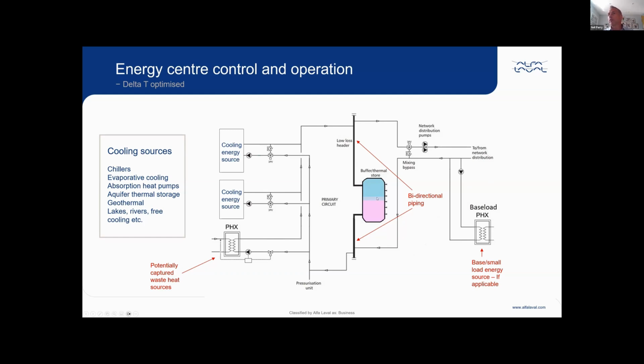So you may not do anything for a while, because you want to be using your thermal store. But when that stratification layer starts to get higher up in the vessel, you would then start another energy source to add additional cooling. And eventually, of course, you end up producing more cooling than you have as a demand. And what happens then is a reversal in the flow direction, and you start to fill that vessel ready for the next big peak. So the stratification layer starts to move down in the vessel.